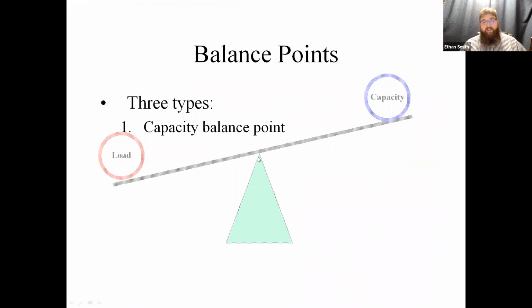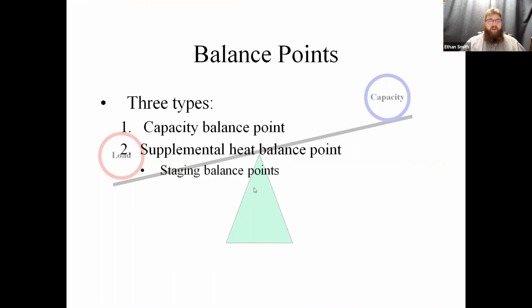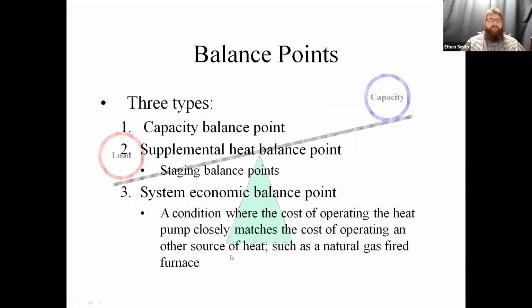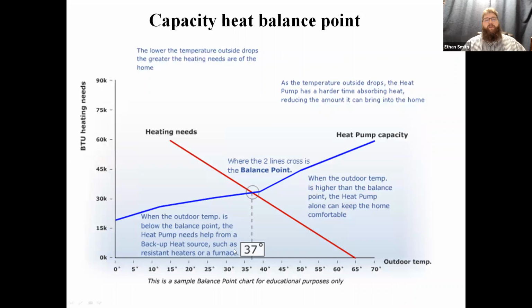So on that note, let's talk about balance points. There are three types of balance points. There's a capacity balance point, there's a supplemental heat balance point, and this can be broken down into staging balance points as well, or there's a system economic balance point. They all operate different ways and achieve different things. So let's talk about capacity balance point.